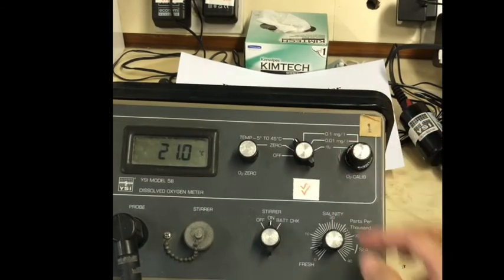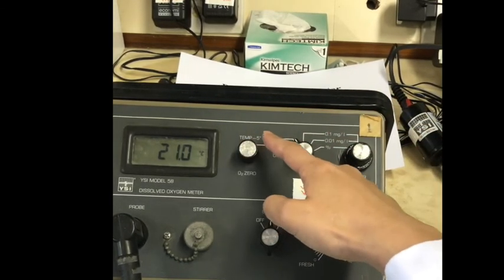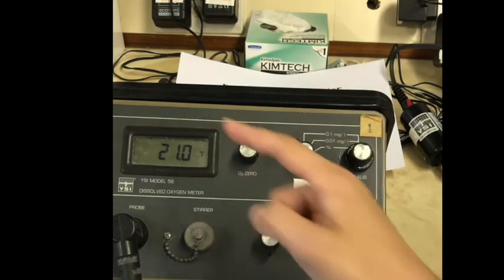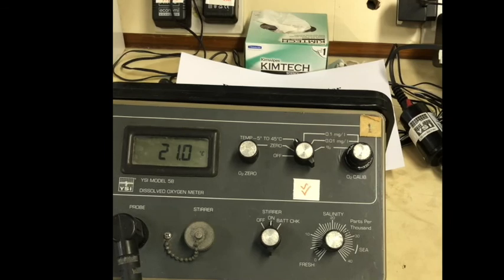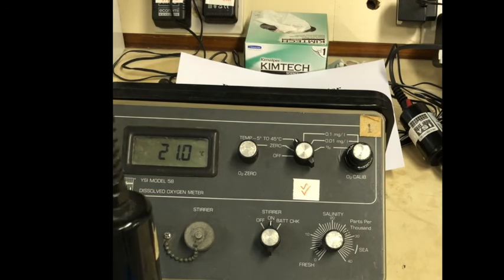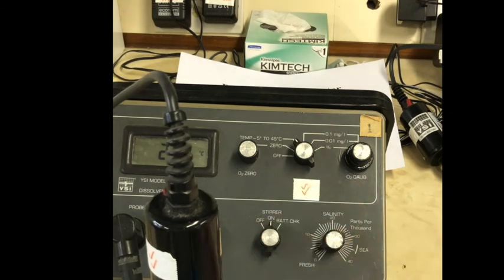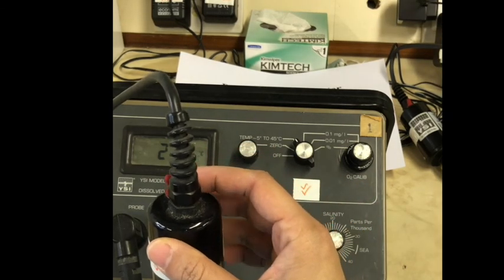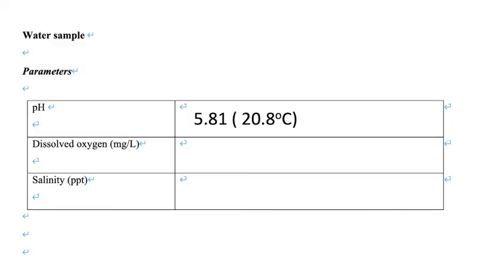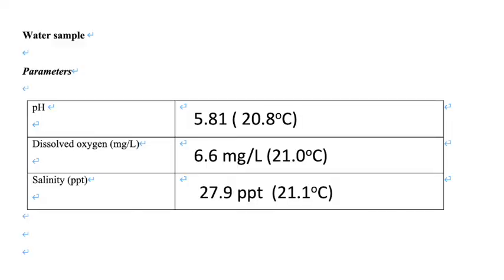For dissolved oxygen, we need to record the temperature of the sample also. Just set the function switch to the temperature, and this is the reading of the temperature of the sample. And the measurement of dissolved oxygen is complete. Turn off the stirrer and discharge the sample solution. After the measurement, just write down the records in the table. The amount of dissolved oxygen in this seawater sample was 6.6 milligram per liter, and the temperature of the sample is 21 degrees Celsius. This is the end of the video.